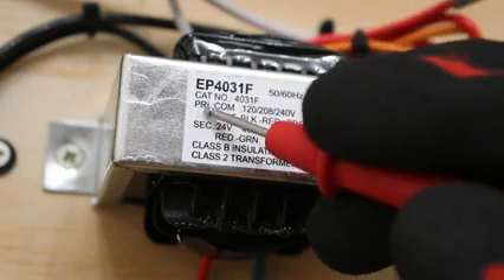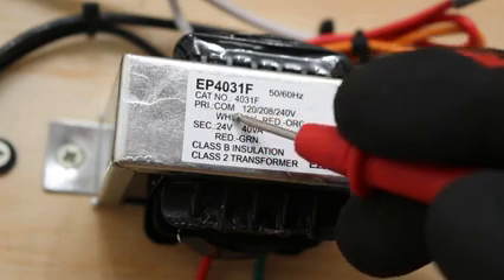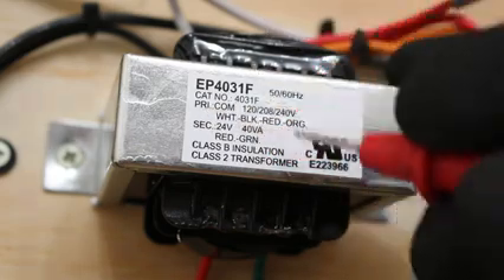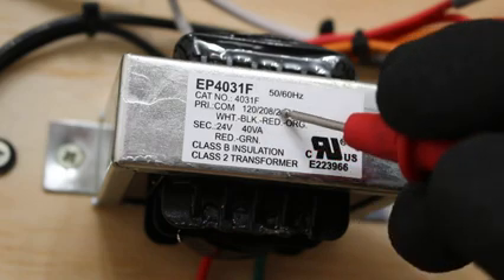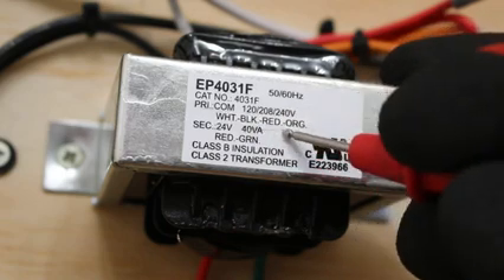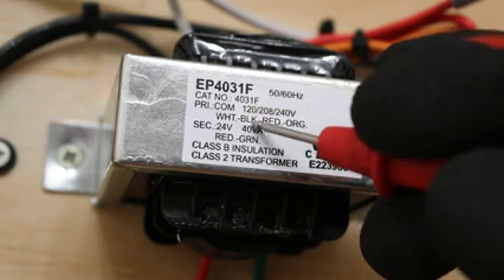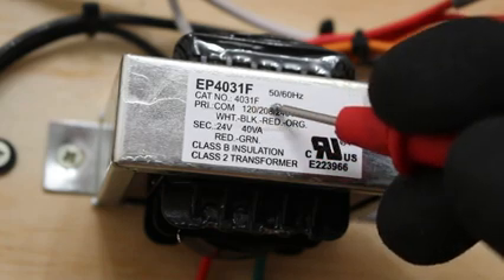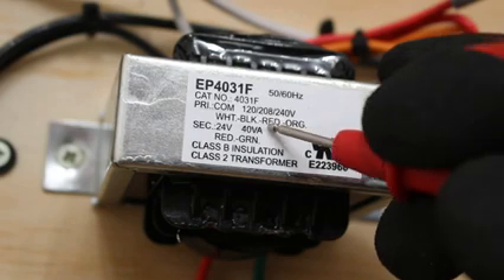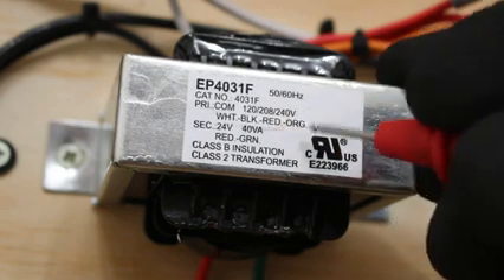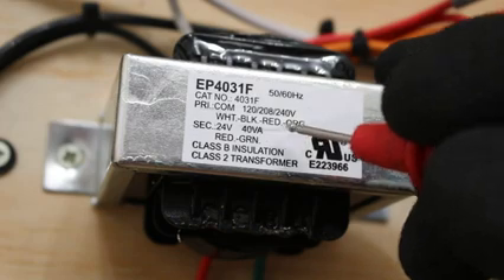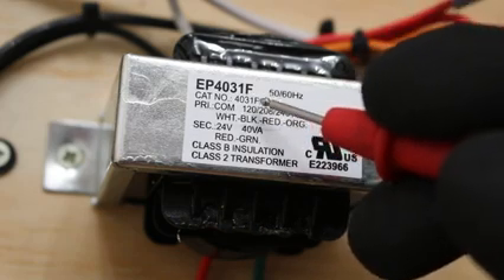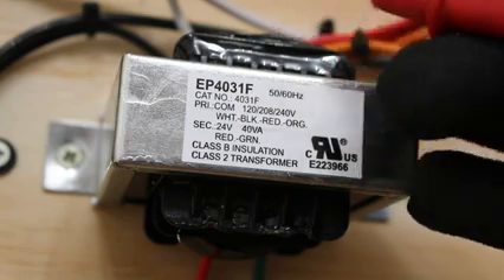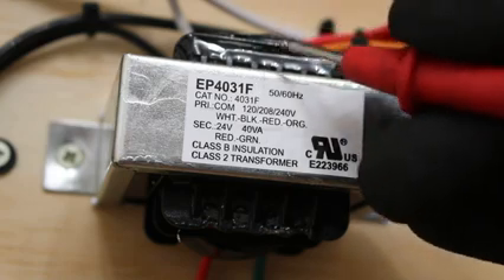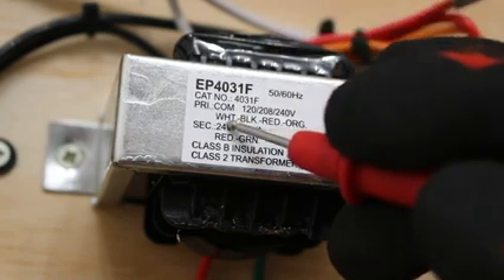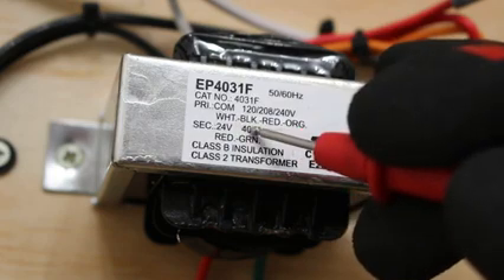Your primary coil is going to have a common, which is your white color. And then we have three other voltages with three other colors. 120 is going to represent the black wire, 208 volts is going to represent the red wire, and 240 volts is going to represent the orange wire. So depending on what the incoming voltage is, that's what you're going to see connected. In this case, we have 120 volts, so white and black is going to be connected here.